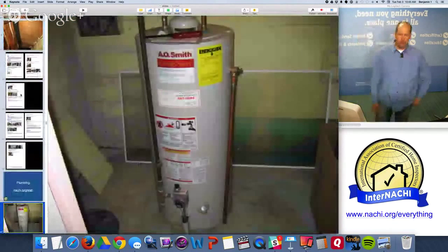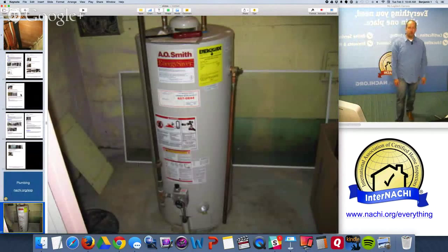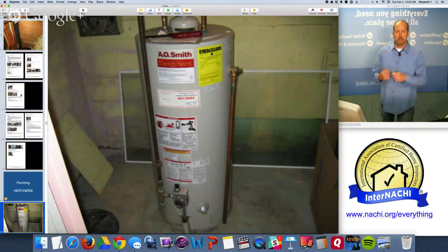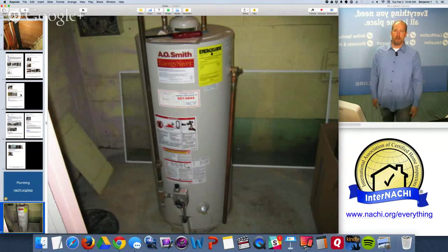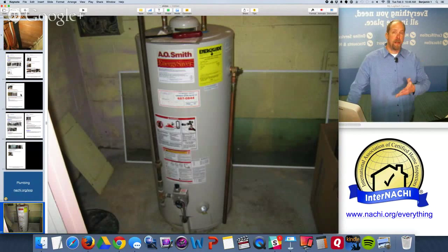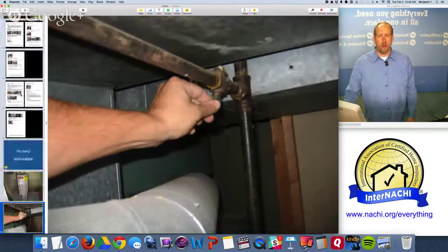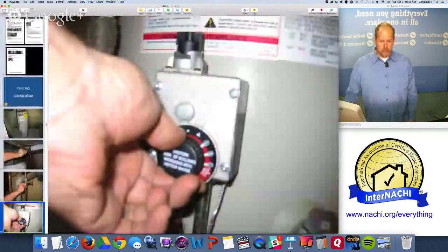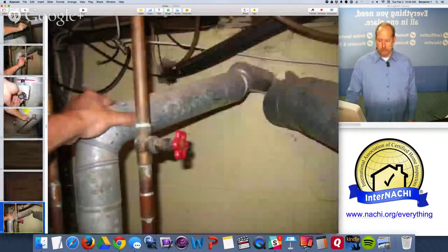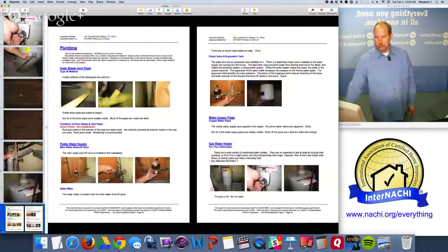For the plumbing system, there's the hot water tank. On top of the tank there may be a flame igniter or matches - someone's been there recently trying to light the pilot light. Why? Did it blow out from back-draft? The gas to the house is shut off, so I don't know. There's a gas shutoff valve, water shutoff valve, temperature control, TPR valve extended to the floor, a 40-gallon gas unit. I note the flue pipe connection and the plumbing - water going out and water coming in.